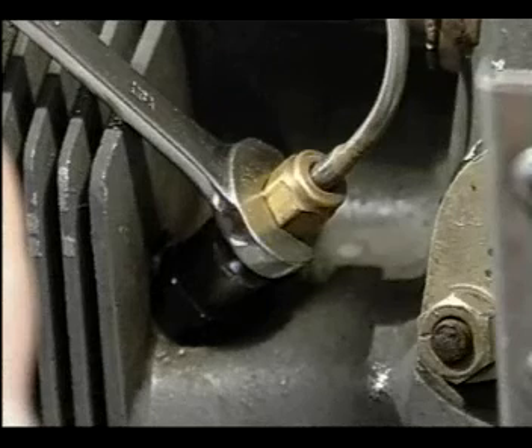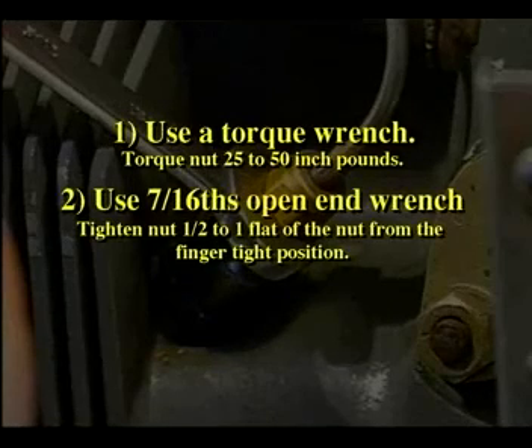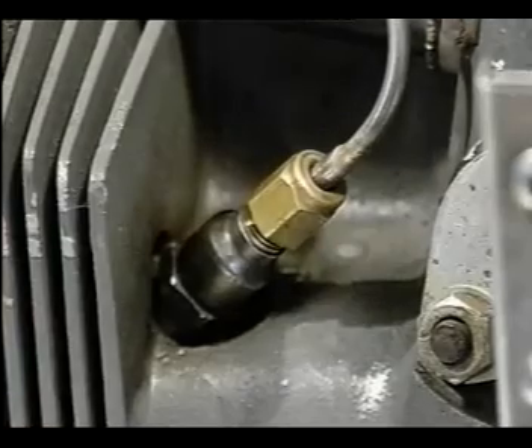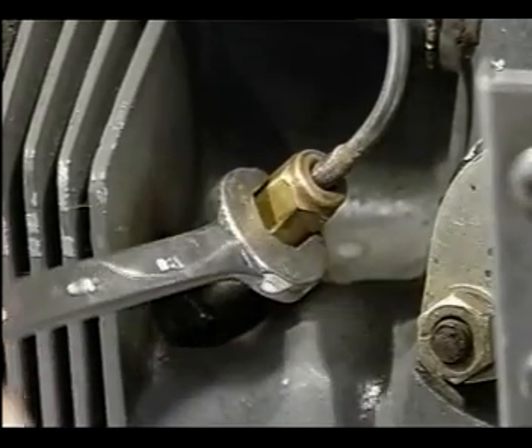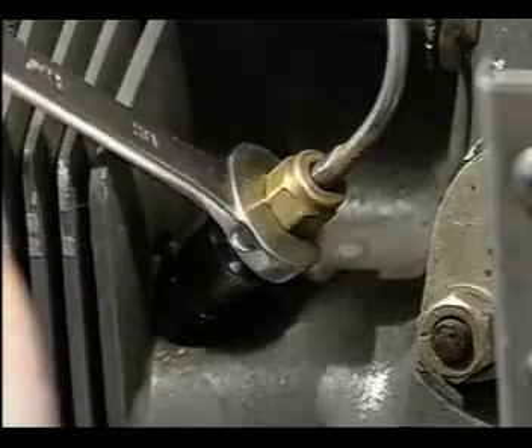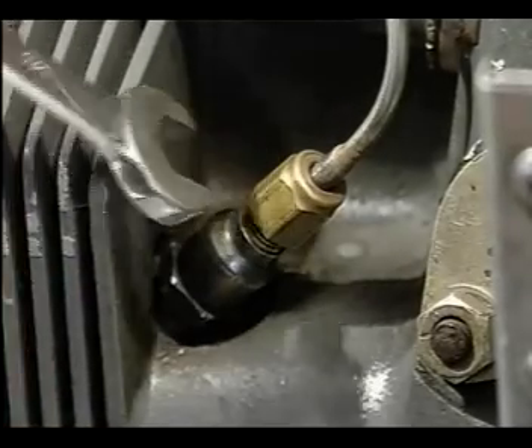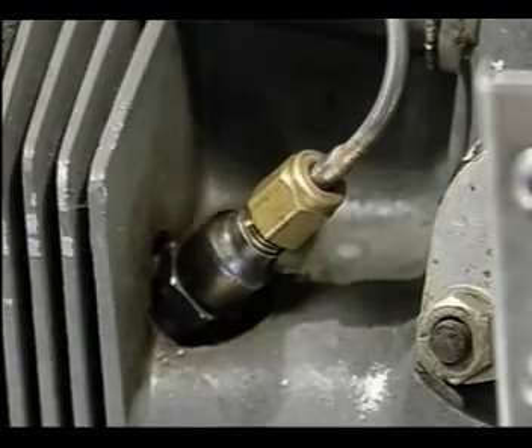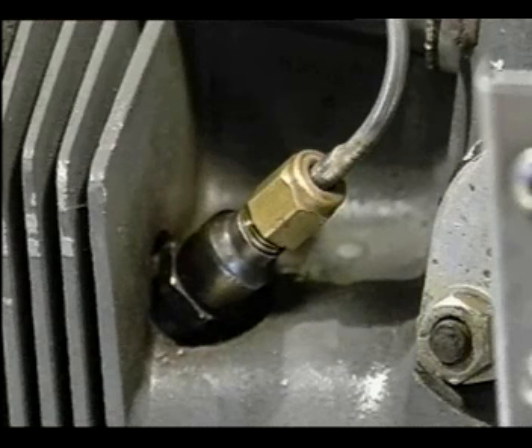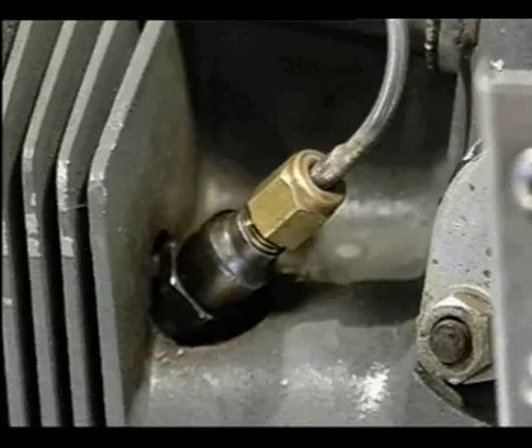Now, you have two options. Try to use a torque wrench with adapters if room permits, and torque the nut 25 to 50 inch-pounds. Or, use a standard 7/16 inch open-end wrench and continue to tighten the nut 1/2 to 1 flat of the nut from the finger-tight position and stop. This technique has proven to provide the 25 to 50 inch-pound torque limit. Exceeding the 50 inch-pound torque limit usually does result in nozzle damage.